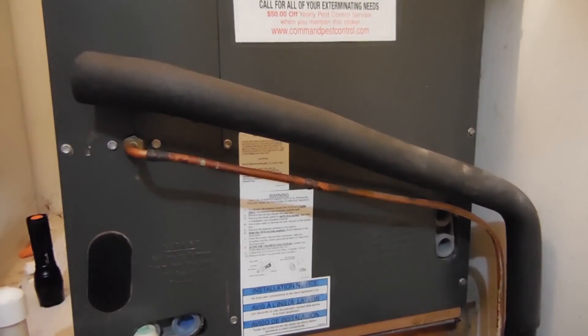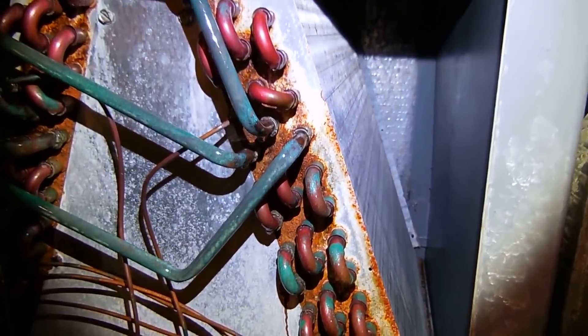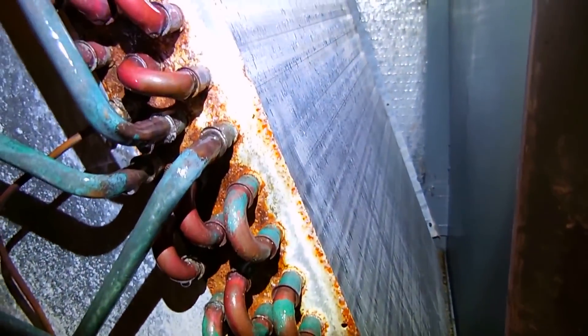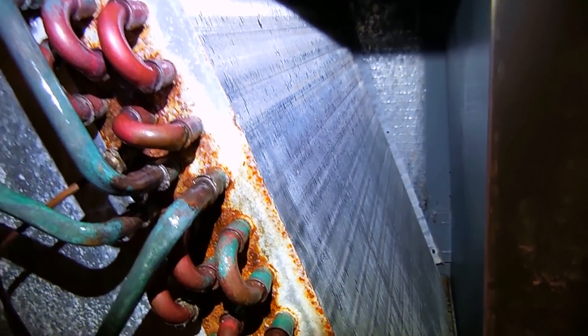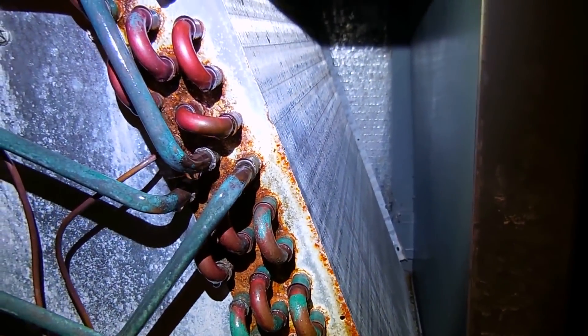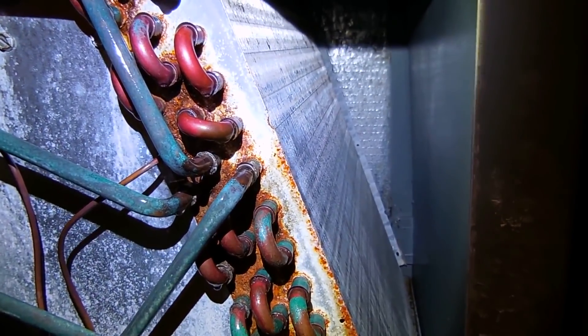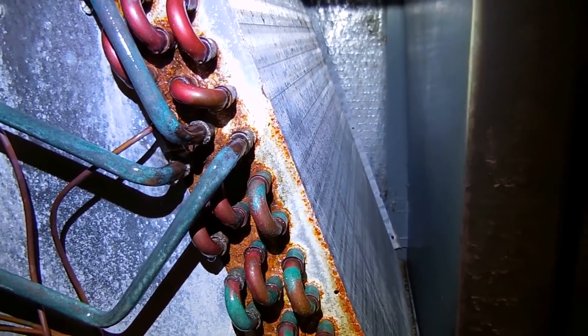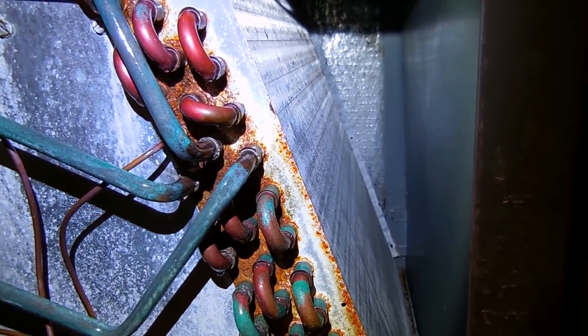Let me open that panel up so we can take a look at the inside. The cover is off and we're looking at the evaporator — it's an A-type. There's the top of it and there's the bottom of the pan. There was a thin layer of ice over here; when I opened this cover it all sheeted off and melted. Now I'm going to turn on the blower motor again because I want to make sure there's adequate airflow going through this evaporator coil.